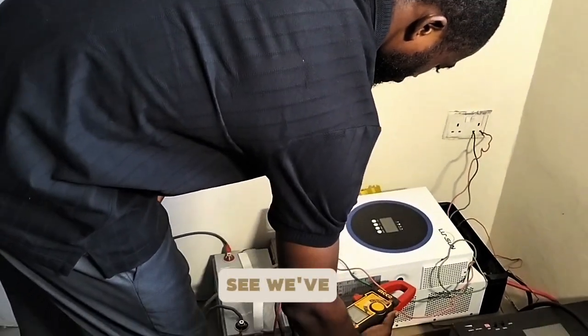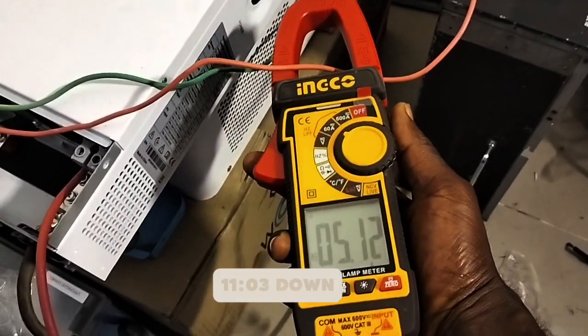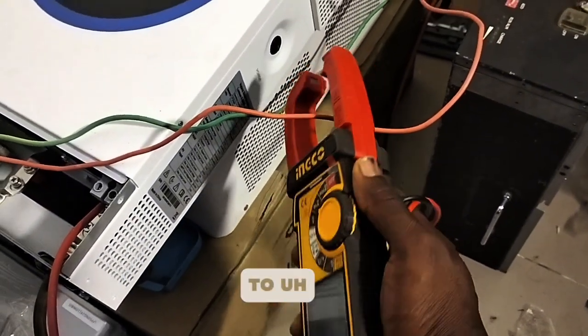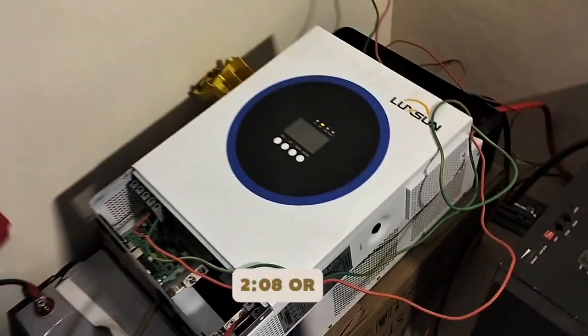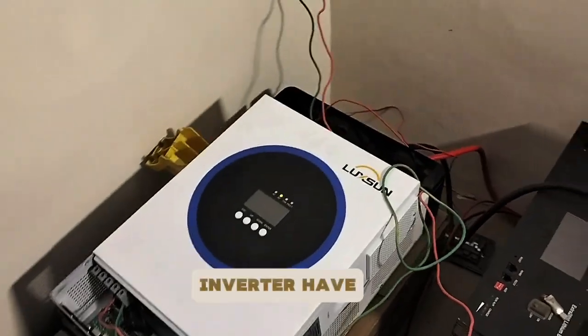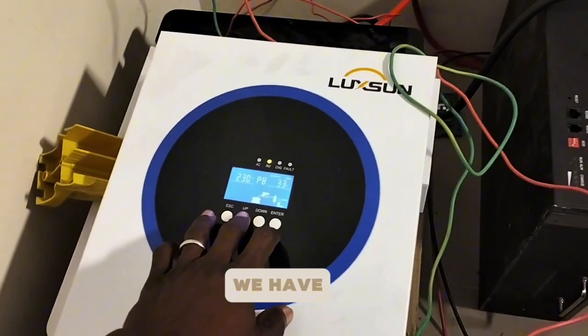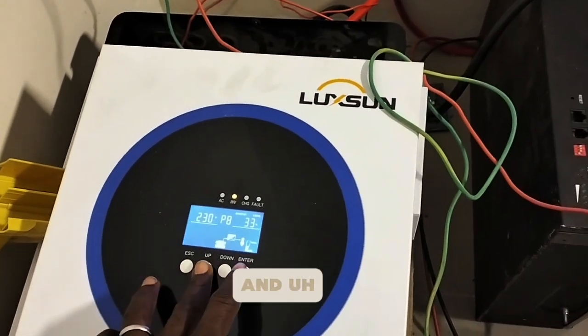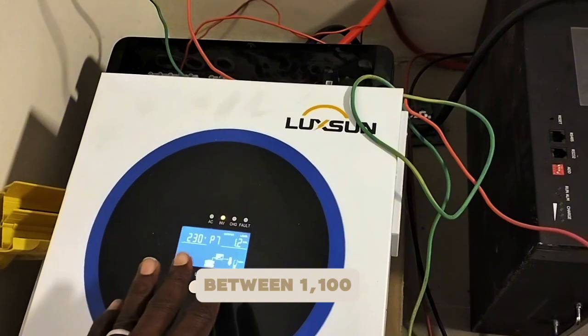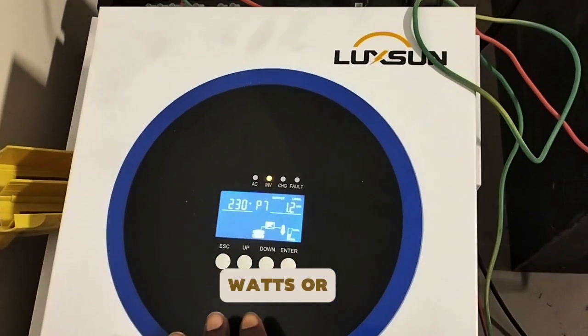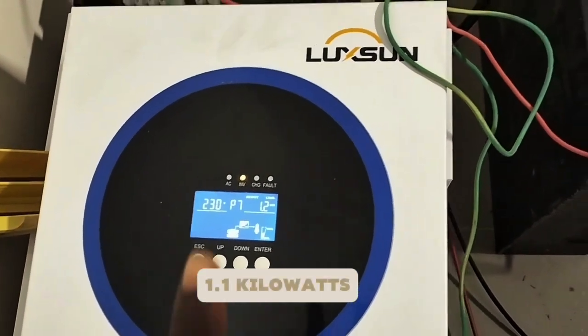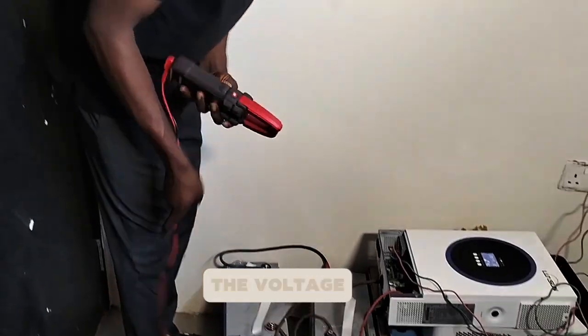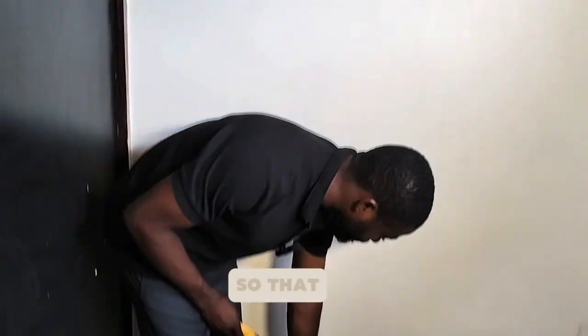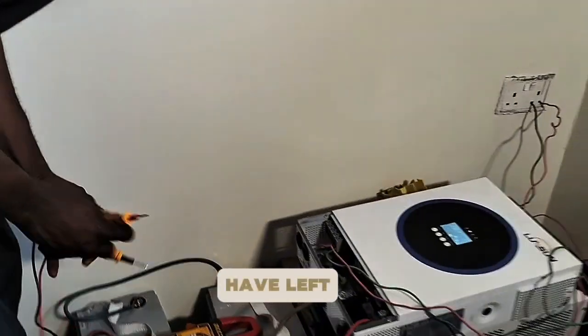You can see we've maintained the same 5.1 amps from around 11:03 down to 2:08 or 2:09, and the inverter has been running. On the inverter screen we have 33% load, and it's fluctuating between 1100 watts and 1200 watts, which is 1.1 kilowatts or 1.2 kilowatts. Let's check the voltage on each battery so that we can predict how much energy we have left on this battery.